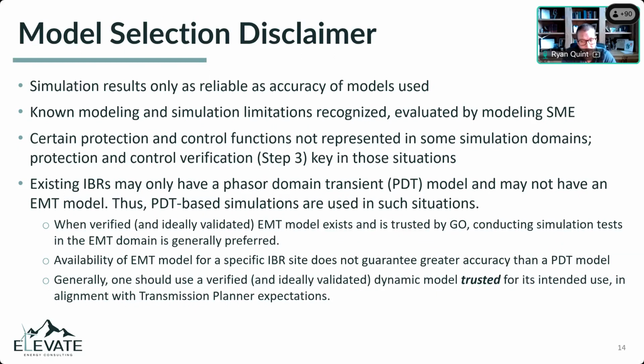So generally what we've said is, especially for legacy sites, all sites are going to have a phasor domain model, some sites may have an EMT model. Really what we want to use is the most accurate, trusted model available. So we don't give preference to one or the other, and definitely don't necessarily say an EMT model is required. But if you have a verified and ideally validated EMT model, it's generally better than using, say, a standard library phasor domain model. But a lot of the existing sites don't necessarily have that EMT model.